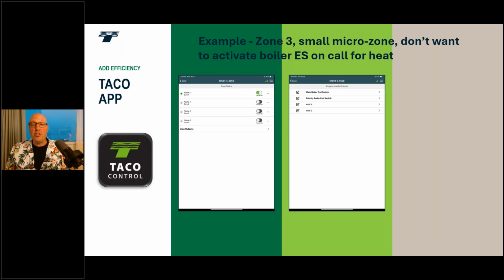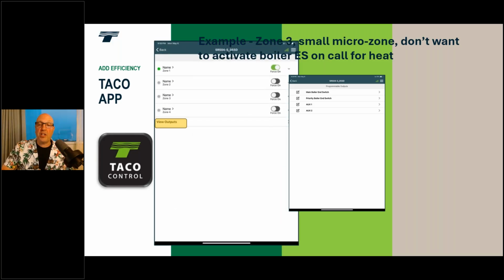So what we can do is click on this view outputs tab down here at the bottom. You see that view outputs. As I click onto that view outputs section, you'll see here I have control over my main boiler end switch, priority end switch, auxiliary 1, auxiliary 2. If I were to click on main boiler end switch, you'll see the first line here says default, the checkbox is on. In default mode, if any one of my zones calls for heat, it's going to close the end switch on the control to tell the boiler to fire.